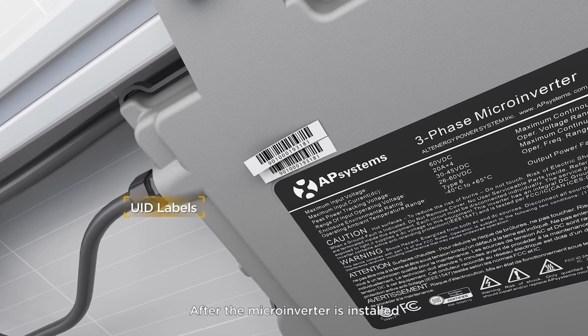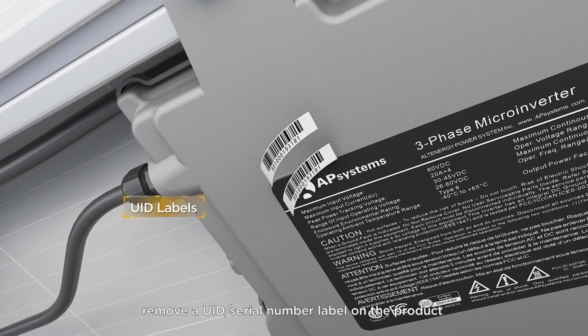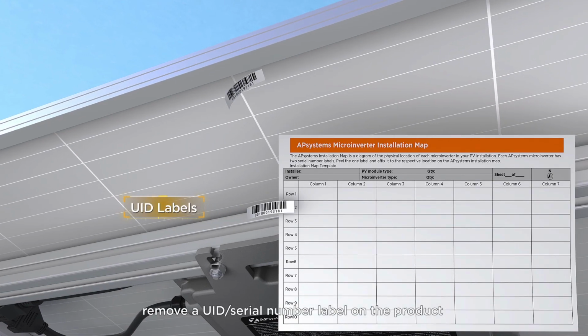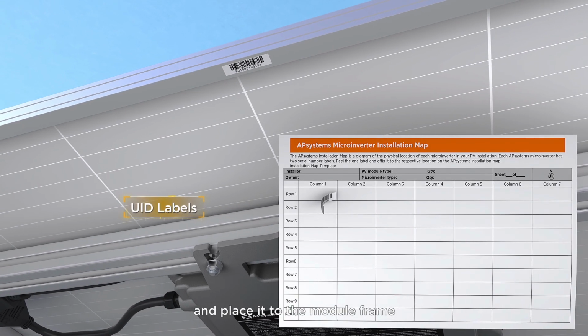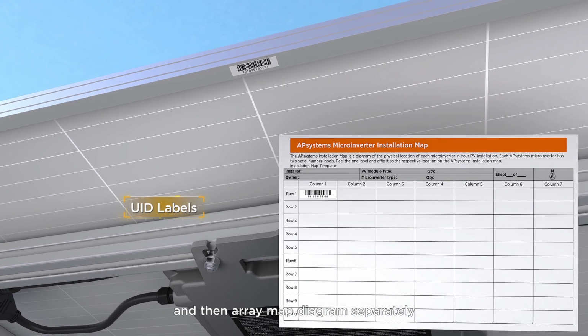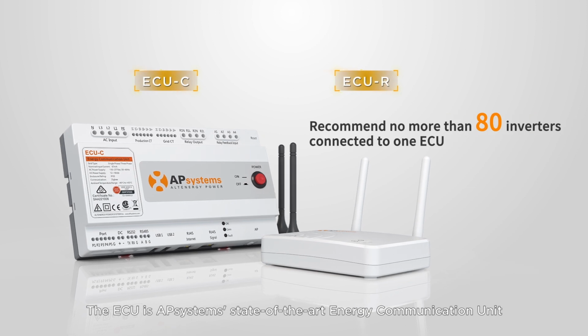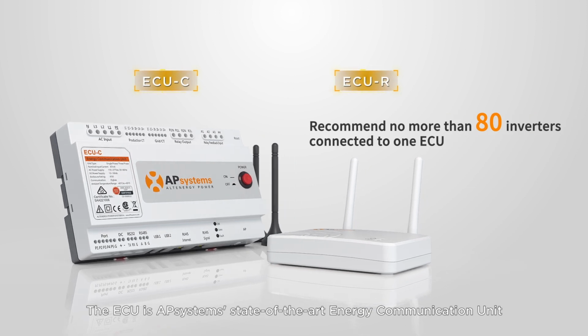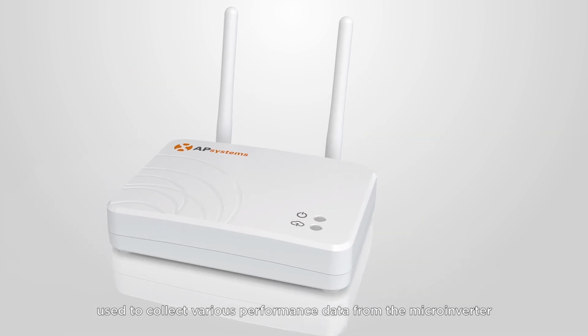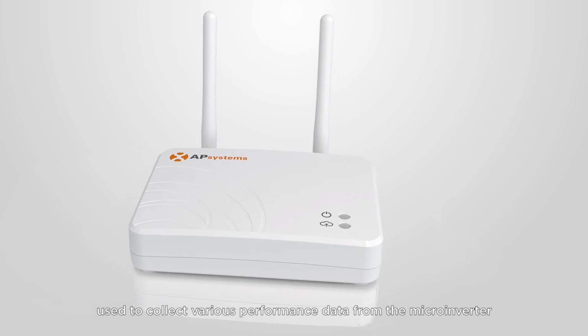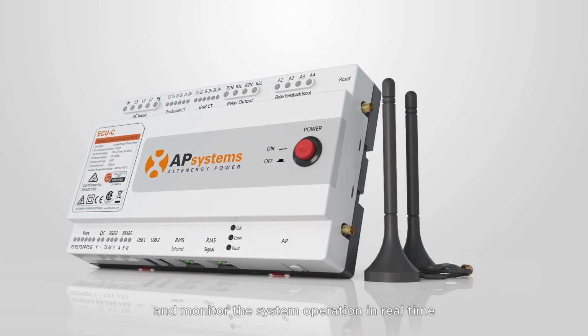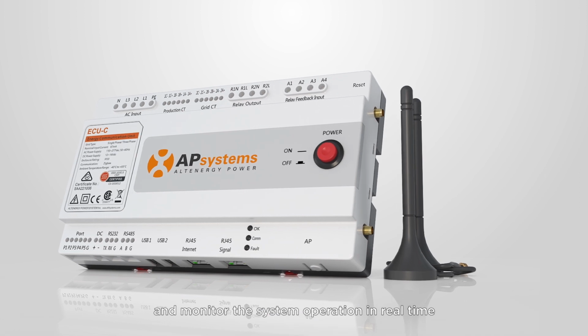After the microinverter is installed, remove a UID or serial number label on the product and place it on the module frame, and then on the array map diagram separately. The ECU is AP Systems' state-of-the-art energy communication unit used to collect various performance data from the microinverter and monitor the system operation in real time.